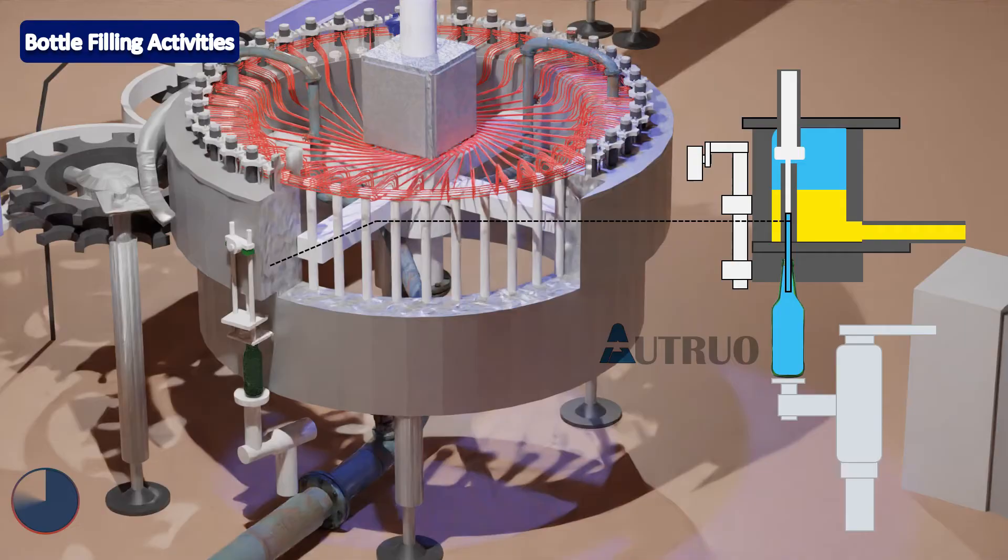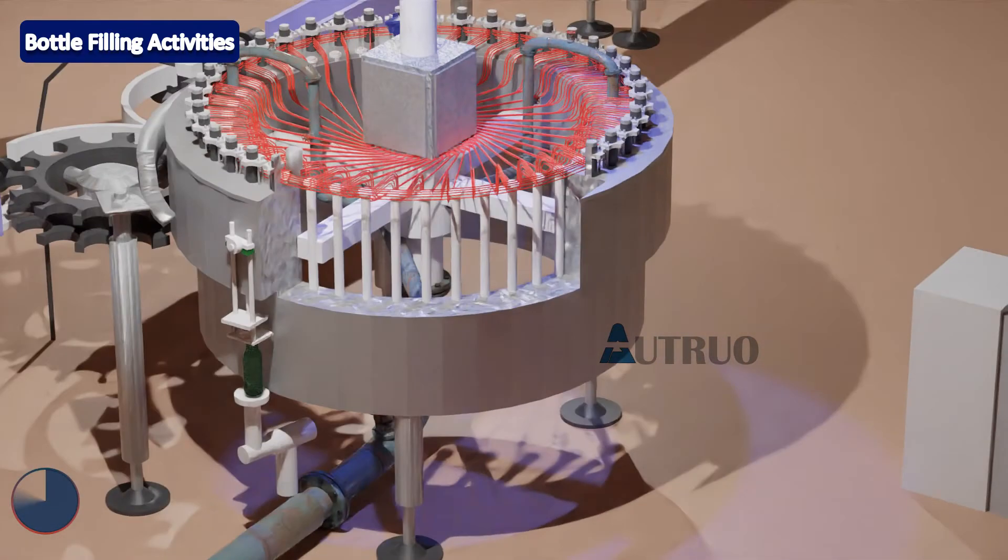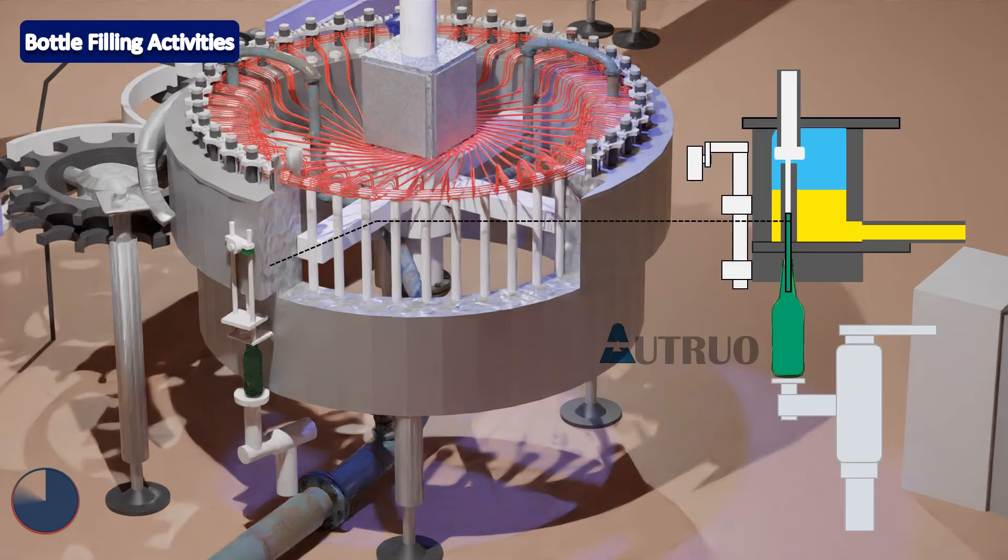When the filler rotation is between 10 degrees to 15 degrees, the PLC will use compressed air to activate the pre-evacuation valves, and removal of CO2 and oxygen will take place within the bottle.